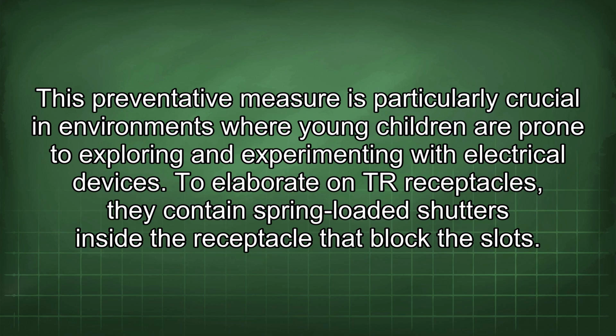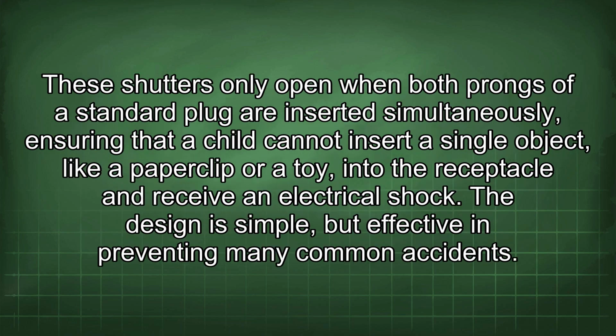To elaborate on TR receptacles, they contain spring-loaded shutters inside the receptacle that block the slots. These shutters only open when both prongs of a standard plug are inserted simultaneously, ensuring that a child cannot insert a single object, like a paperclip or a toy, into the receptacle and receive an electrical shock. The design is simple but effective in preventing many common accidents.